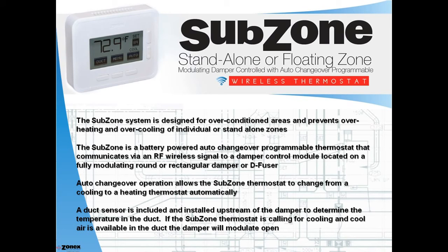We've been talking about VVT systems, but Zonex can also provide a standalone or floating zone solution for areas that are overheated or overcooled with our subzone. Subzone is a wireless, programmable, auto changeover thermostat with integrated duct sensor that controls a fully modulating standalone damper. Again, this is a standalone control that operates independently and does not control the HVAC equipment.